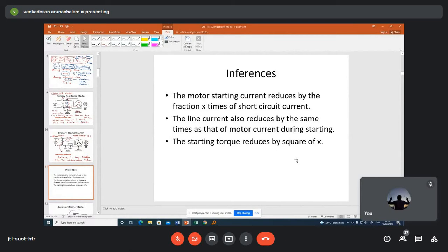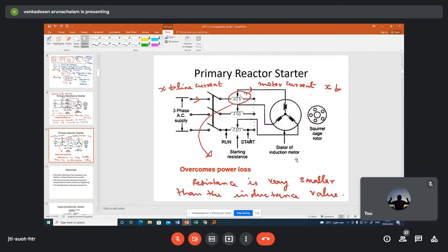So the motor starting current reduces by a fraction X times, and the line current also reduces by the same times as that of the motor current during starting. If you see here, this is the line current. The current which is flowing in this terminal is the line current, and the current which is flowing in this terminal is the motor current. Okay, so this is the line current which is flowing here, that I have shown in red color. This is the line current which is flowing in the input side of the starter, and this is the motor current that is flowing in the output side of the starter.